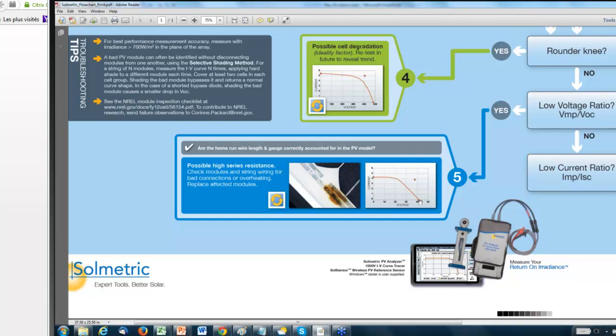And we can detect really small amounts of this. This is a really gross effect here. But what tends to cause that, if there's no steps in the curve and you're seeing this, this is a sign that you have excess series resistance somewhere in your string circuit, in your PV source circuit. We've never seen a case where that's caused by the connection between the alligator clip and the bus bar. It's always somewhere else.